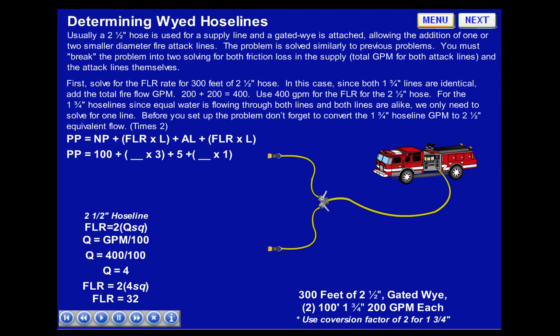FLR equals 2Q squared, and Q equals GPM over 100. In this case, GPM is 400 for both lines divided by 100, so Q equals 4. Friction loss rate equals 2 times 4 squared, or 32 per 100 feet of hose.